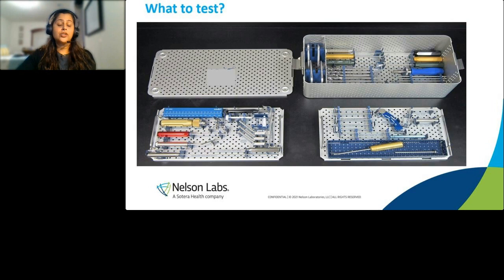Now, I'm not sure if everybody's aware, but when we see a tray like this coming for a validation, we're not testing the entire tray. We do select a worst case device. And how do we select a worst case device out of this tray? There are probably so many instruments in there, and we would have to pick what we, with the manufacturer, think is worst case. And the idea here is that if you choose one or few instruments out of this tray that have the worst case features, designs, lumen size, and if I can clean that with the instructions for use provided by the manufacturer, then I can clean the rest of them because they fall under that umbrella for testing.